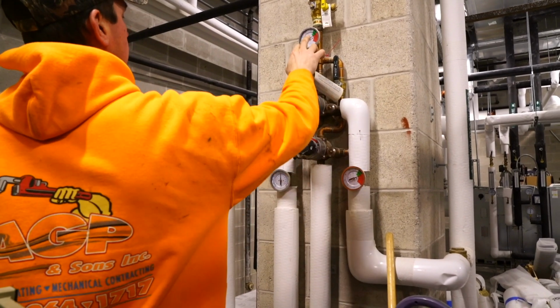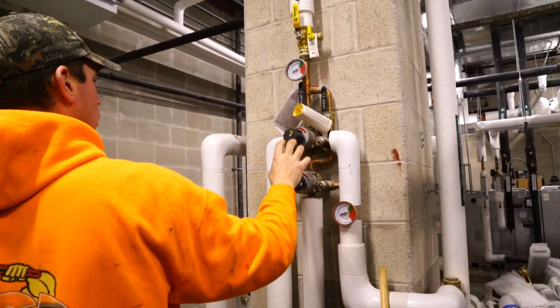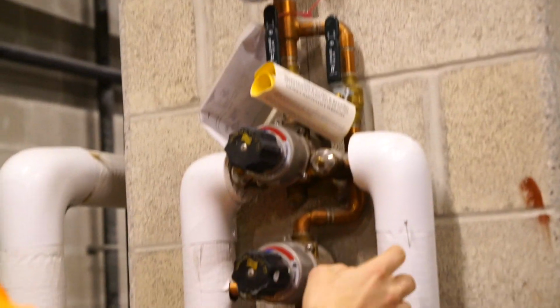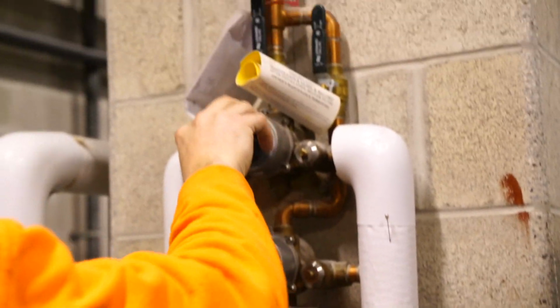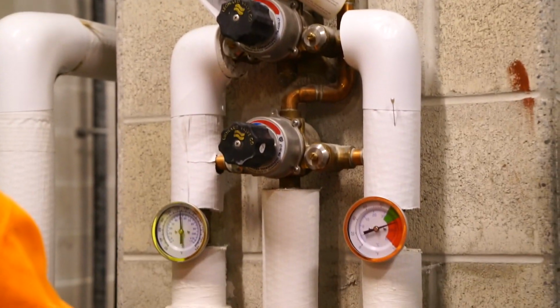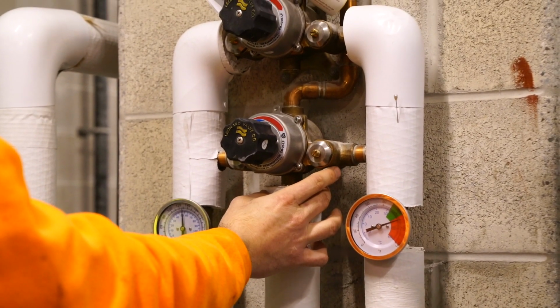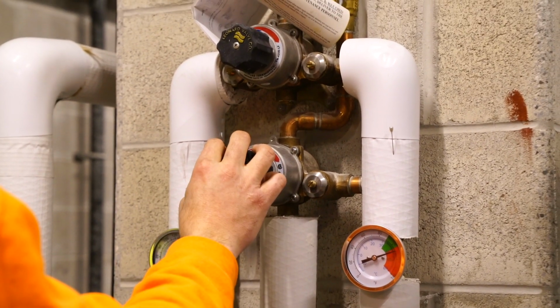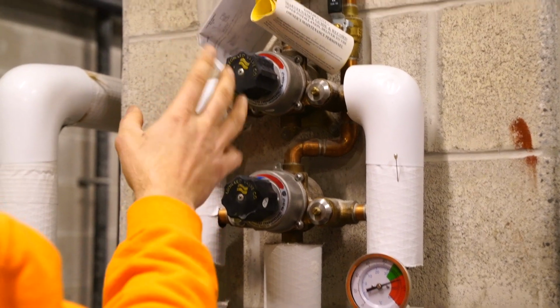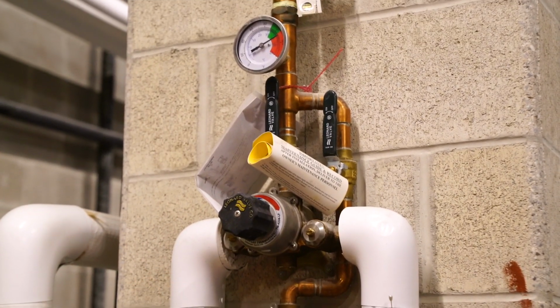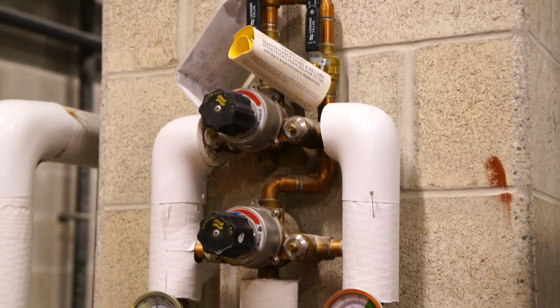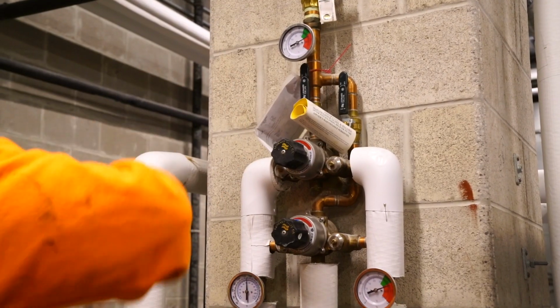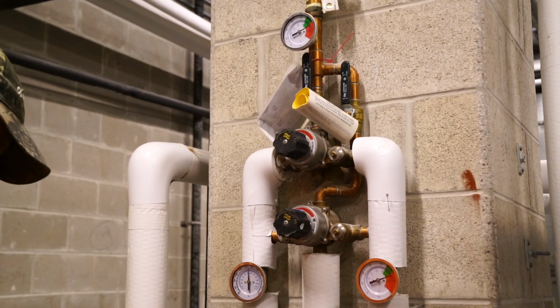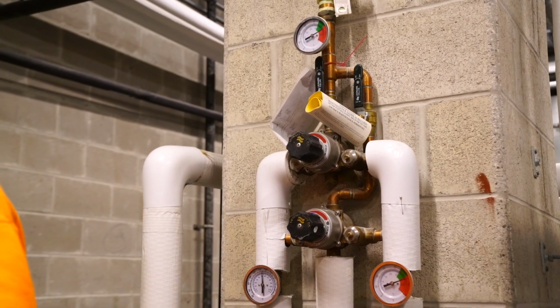I already have it set, like I said, to 110. These are your adjustments for your hot and cold coming in. This is your adjustment for that. And then as far as your recirculating line coming back in, dumping into here, this is your adjustment for that. This took me a couple days to really tweak it. You know, you gotta let the water run. So I kind of have it set to 110. On your hot side coming out, you have your isolation valve to shut off the water.